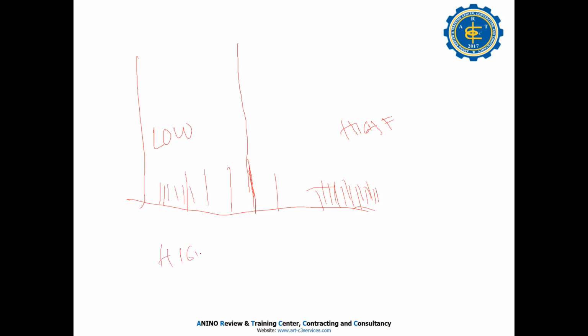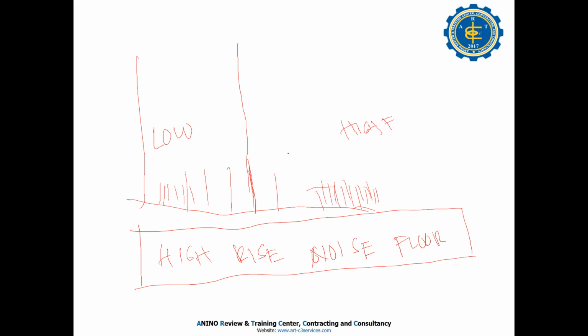High rise noise floor. That's when we consider that the problem is the blade pass frequency. Blade or vane, they are the same, vane pass. If there is no high rise noise floor like this, here or sometimes here, no, that is not vane pass or vane pass frequency.